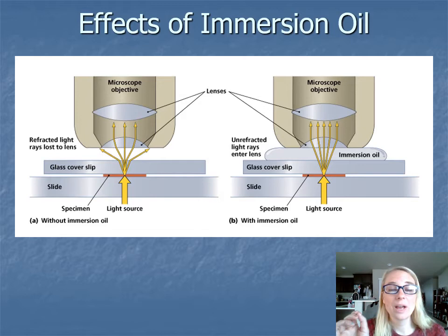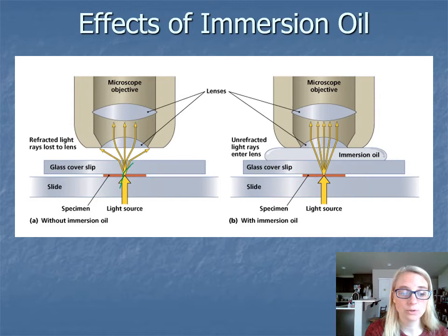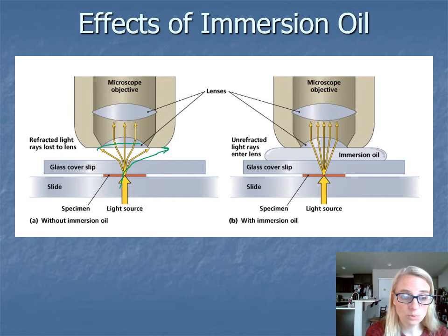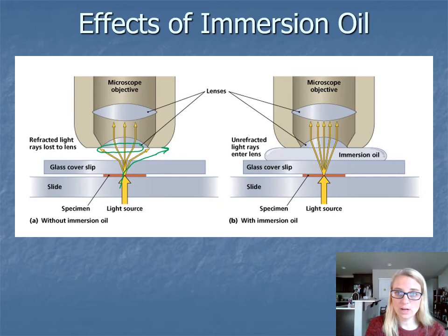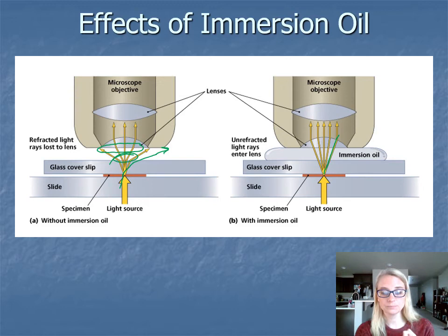When looking at bacteria under oil immersion, bacteria are really small and we need the oil immersion objective to see their characteristics. Light refracts as it passes through different media — air, glass, specimen, glass — and with a very small objective opening, some light can be lost. By placing a bead of immersion oil and putting the lens directly into it, the oil has the same refractive properties as glass, so light goes straight up into the objective instead of bending away. Only use immersion oil on the 100x objective — never on any other objective.